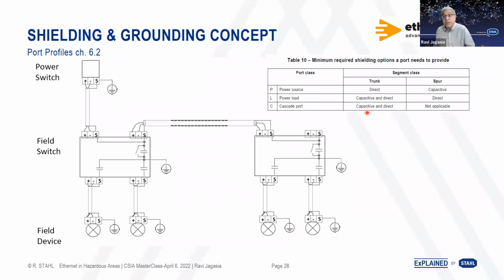The shielding and the grounding concept, again, required. It's a minimum requirement from the Ethernet-APL engineering guide, and that is something which I'll come to later. So you can see the shielding being done, the grounding at the power switch, at the field switch, at the field devices. And of course, these groundings are all equipotential. So what you have in the field and what you have in the control room have to be at the same equipotential. Some of the concepts of what kind of shielding or grounding you can do is through capacitance or direct, depending on trunk and depending on the SPUR that you are using when you're using the field.